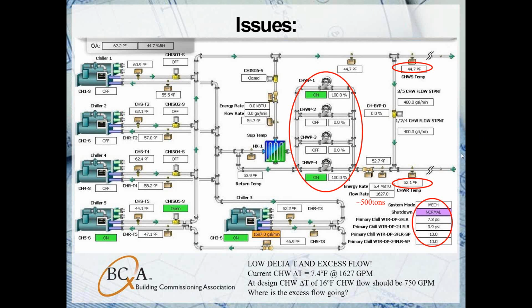use one of the 400-ton chillers that was originally intended for the series counterflow as the first stage of mechanical cooling. And what we more than made up for the loss in efficiency by fixing that over-pumping problem, by optimizing the condenser water reset at the cooling towers. So more than made up for it there. I hope that answers that question.